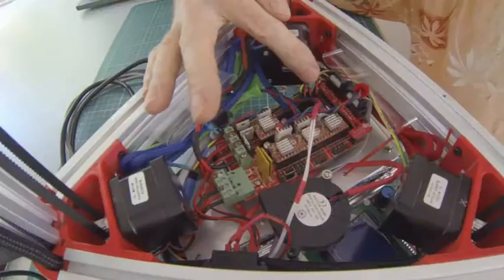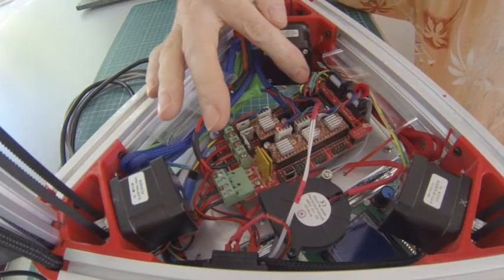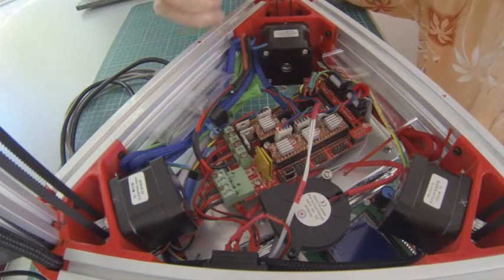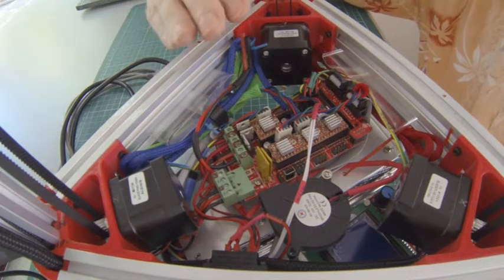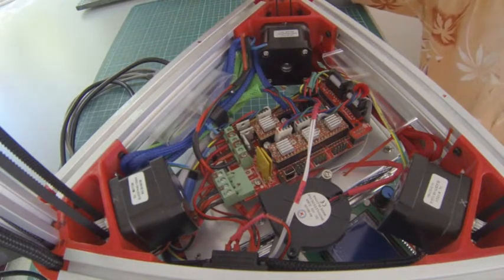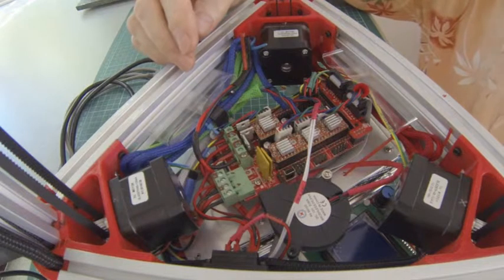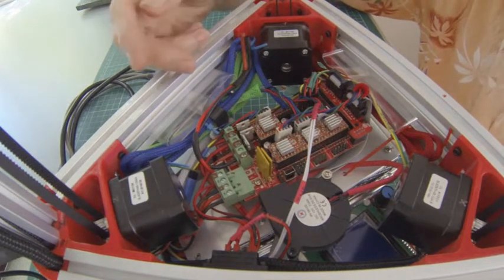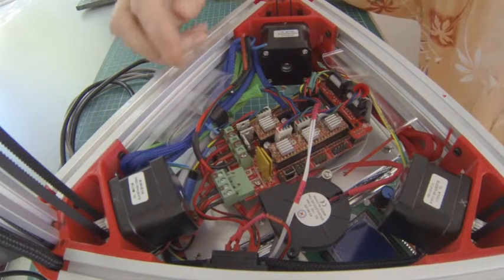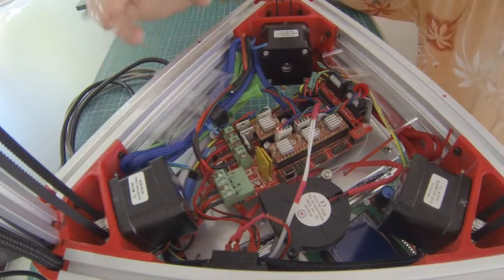The reason you can pick that up is that when you do the calibration after assembly and go through the manual, it tells you to run a test, an M119, which shows whether they're open or closed, or not open and not closed - and it's because the actual original drawings are wrong.